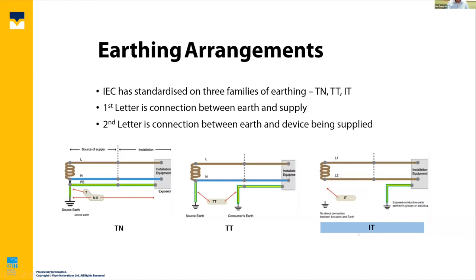So for an IT system, the first letter I stands for isolated, so the supply is isolated from earth. And the second letter, T, in this case stands for terra. Now, apologies for all you French speakers, because that was my impersonation of the word terra, which is French for earth. So if it's a T, it means it's connected to earth. So in this middle one, you can see that the supply, the first letter is T, the supply is connected to earth, and so is the consumer, connected directly to earth.